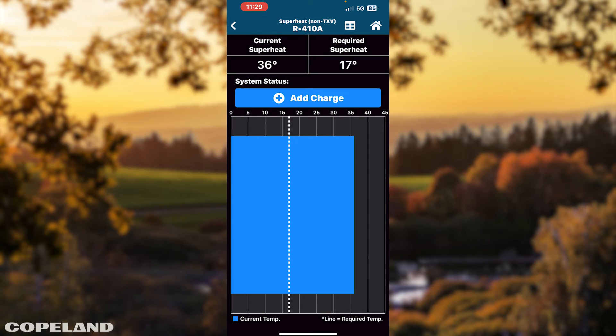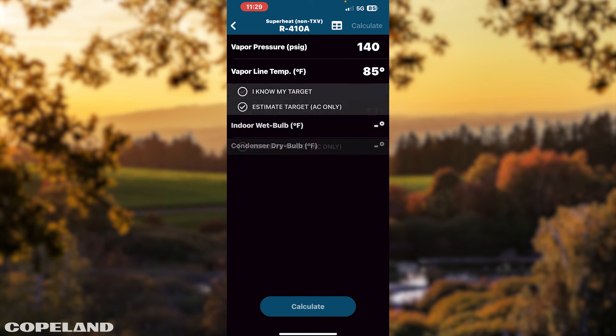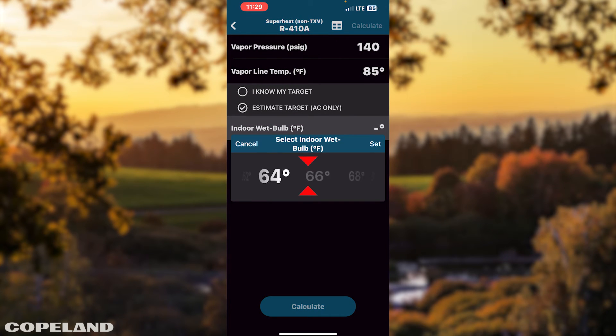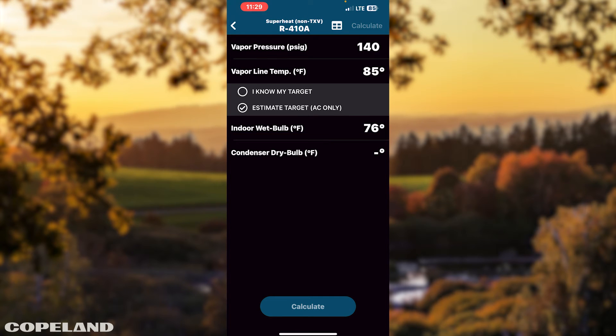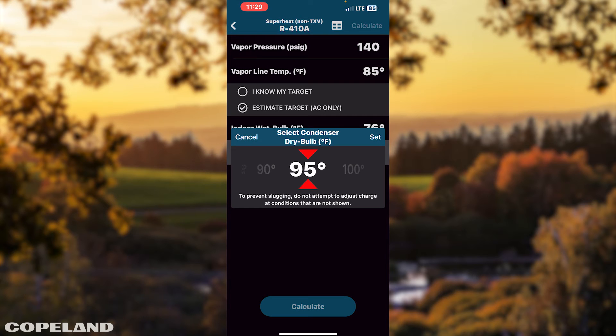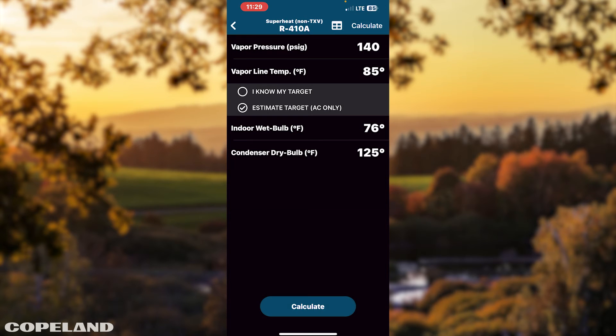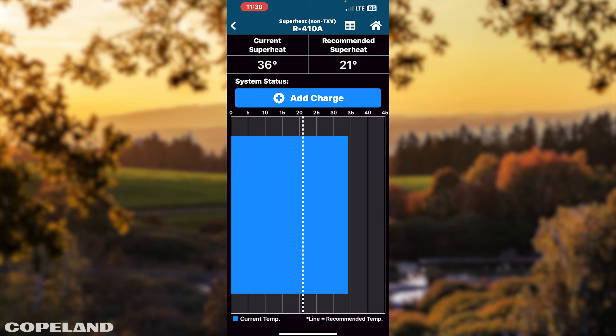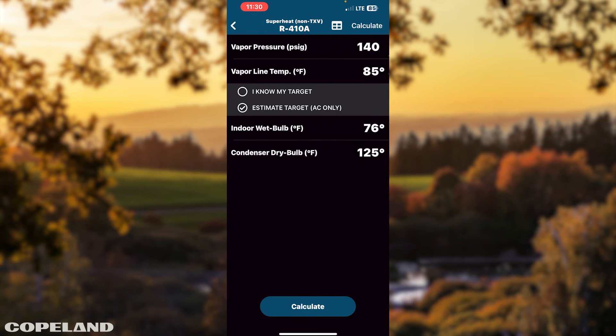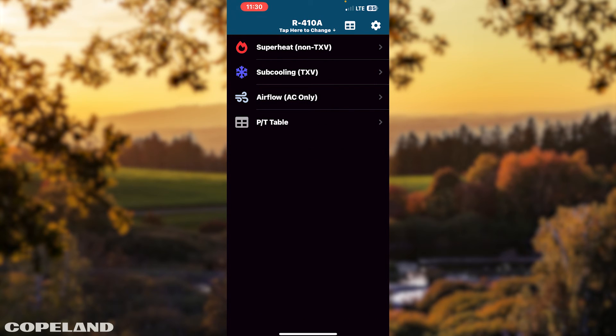If you select Estimate, tap Wet Bulb Temperature. Scroll right or left to select the desired temperature. Tap Set to enter temperature. Next, tap Condenser Dry Bulb Temperature. Scroll right or left to select the desired temperature. Tap Set to enter temperature. Tap Calculate. In the system status window, follow charging instructions. Tap the back arrow twice to get back to the landing page.